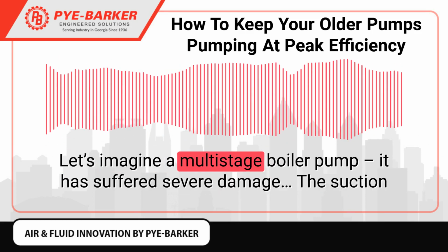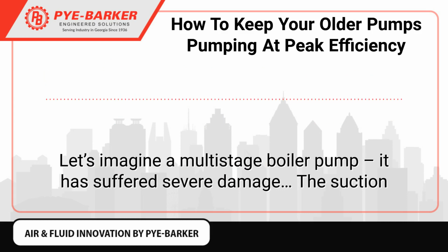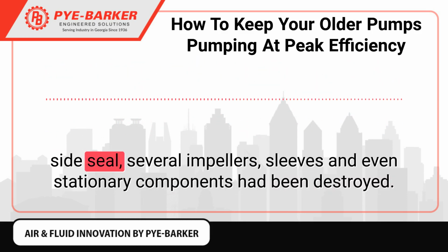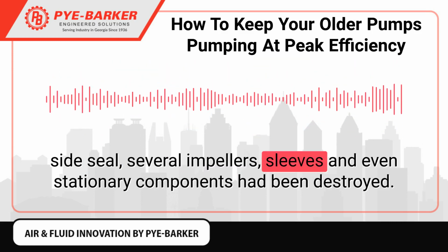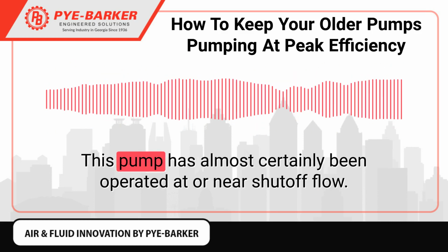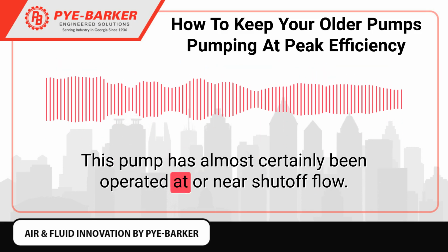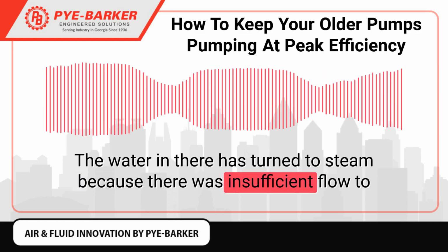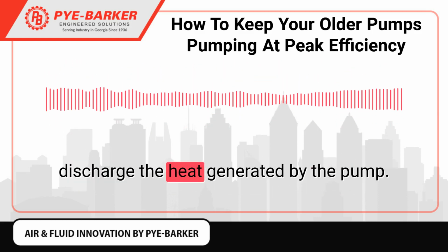Let's imagine a multi-stage boiler pump. It has suffered severe damage. The suction side seal, several impellers, sleeves, and even stationary components have been destroyed. This pump has almost certainly been operated at or near shutoff flow. The water in there has turned to steam because there was insufficient flow to discharge the heat generated by the pump.